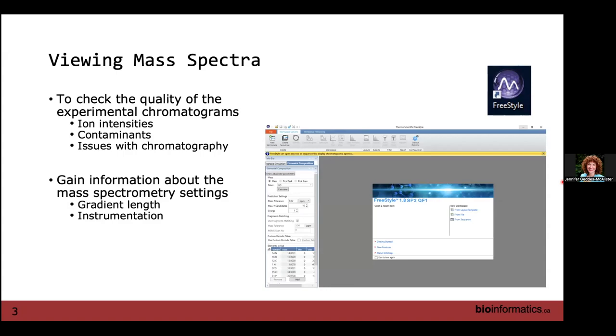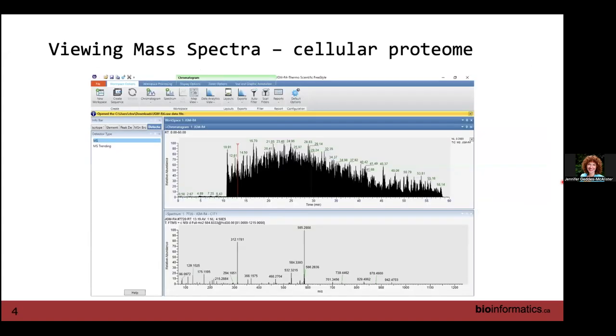You can also gain information about potential contaminants and chromatography issues. Freestyle also stores mass spec settings — like gradient length — within the raw files. So if you did an experiment three years ago and now want to publish, you can open the file and find out whether you used a three-hour or half-hour gradient and which instrument it was on. It's very useful for catching up when time has passed since you did the experiments.